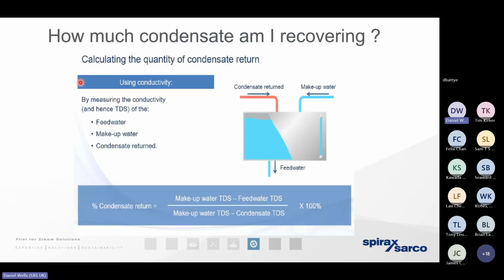Okay, so we know the benefit of recovering that condensate. It's high temperature hot water. It's a byproduct at the heat exchanger. We need to get rid of it quickly because it can be a barrier to heat exchange. And we need to get it out of the infrastructure quickly as well, because if not, we're going to get steam that is deteriorating and degrading. But it can also be a burden of maintenance if we're not getting the moisture out of the steam. But if we can get it back to the boiler house, we know that there's a huge, huge benefit in putting that high temperature hot water back into the hot well. So it's there on standby for whenever the boiler needs to produce steam.